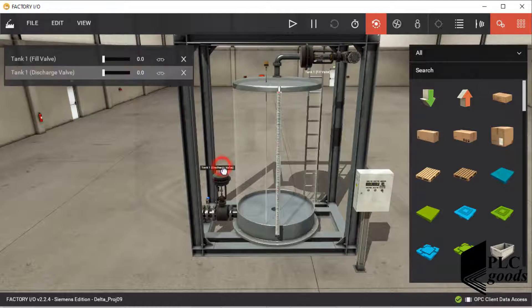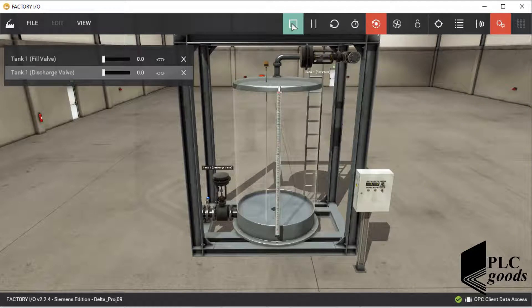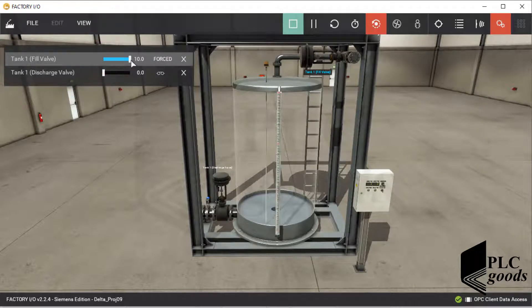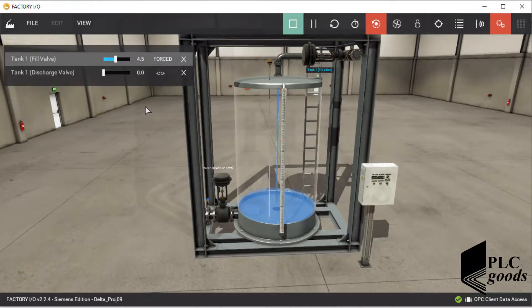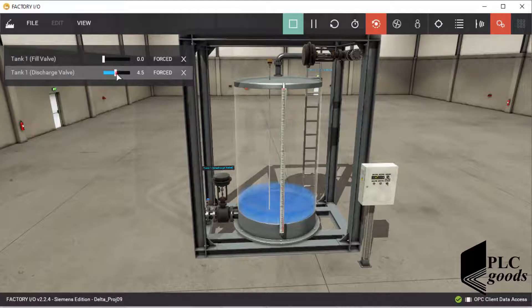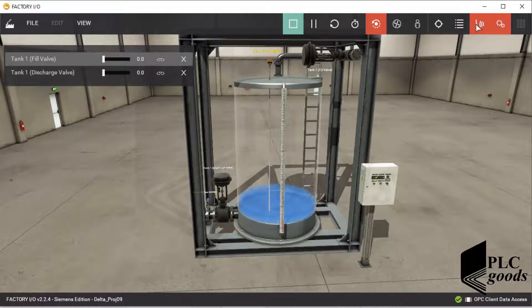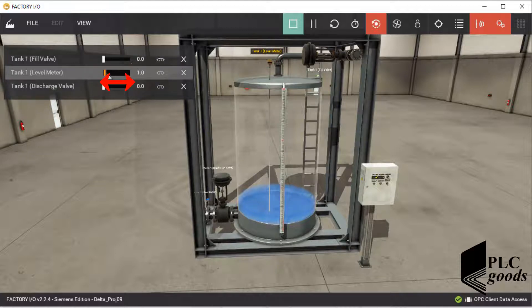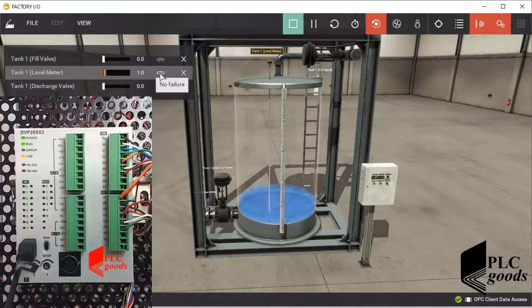Note that this water tank has two inlet and outlet valves to fill and discharge it. These two valves are controlled by a voltage between 0 to 10 volts. The tank also has a level meter — it produces a voltage between 0 and 10 volts when the water level changes between 0 and 3 meters. In real conditions, equipment must be connected to real inputs and outputs of the PLC. But for this simulation, I used memory addresses to connect them to my PLC via the OPC server.